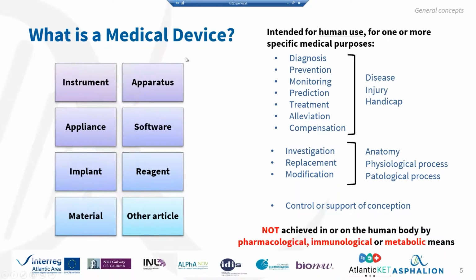Okay, it is important to keep in mind always that the mechanism of action of this device cannot be achieved through pharmacological, immunological, or metabolic means. Okay, it's truly important to keep this in mind in order to qualify your device as a medical device. Okay, if the main mechanism of action is pharmacological, the product will not be considered a medical device, but a medicinal product.